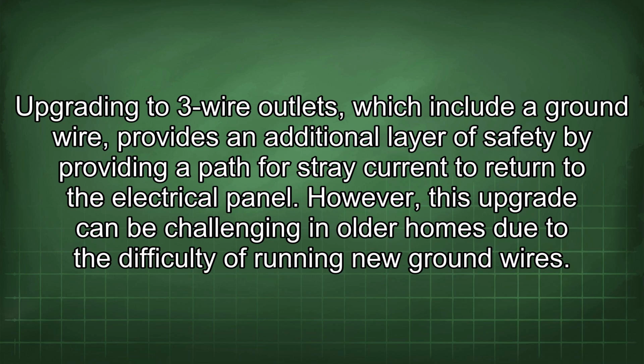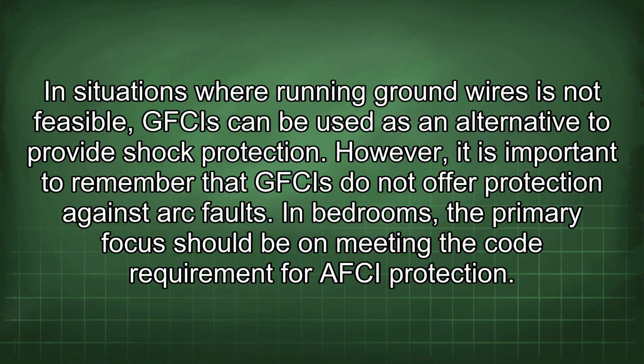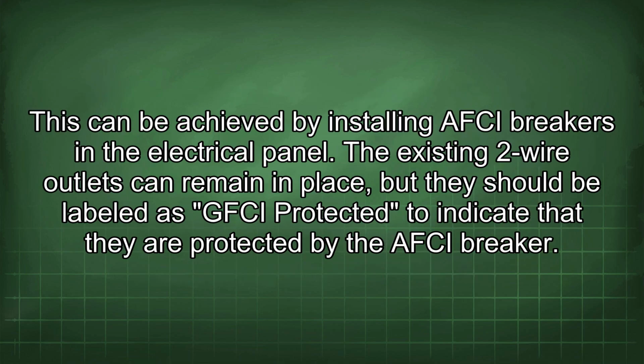However, this upgrade can be challenging in older homes due to the difficulty of running new ground wires. In situations where running ground wires is not feasible, GFCIs can be used as an alternative to provide shock protection. However, it is important to remember that GFCIs do not offer protection against arc faults. In bedrooms, the primary focus should be on meeting the code requirement for AFCI protection. This can be achieved by installing AFCI breakers in the electrical panel. The existing 2-wire outlets can remain in place, but they should be labeled as GFCI protected to indicate that they are protected by the AFCI breaker.